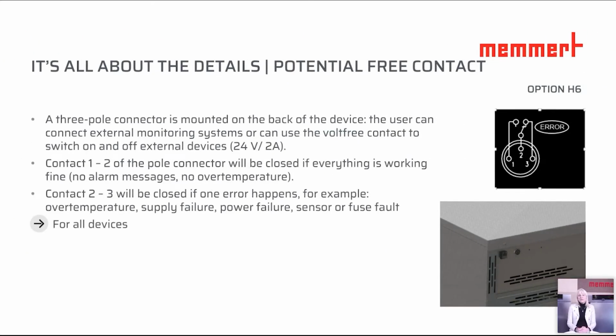Potential free contacts, floating switch contacts. These are simple relays switching on and switching off. Depending on which contacts are closed, we can create error messages. And this is the H6 option for combination error messages. So if contacts 2 and 3 are closed, there occurs an error. And this is in regard to loss of voltage or over temperature, under temperature if it's a twin glass model, humidity alarm, mechanical temperature limiter, or fan speed in case the unit is equipped with this accessory, and error sensor PT. This is a 3-pole connector, and this connector is mounted at the rear of the device. And here you can also connect external monitoring systems, or you can also use it for volt-free contact to switch on external devices.